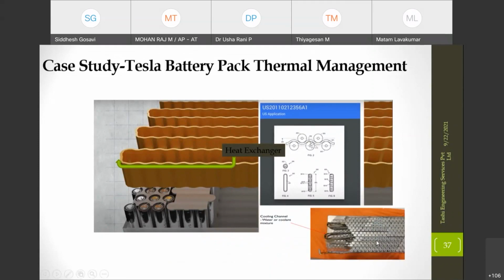From the top view, we can see all the cylindrical cells are in contact with this area, at an angle of contact of 25 to 30 degrees. Through this contact, within the cold plate, the water ethylene glycol line is passing, not refrigerant, and that's how heat is taken away from the cells.